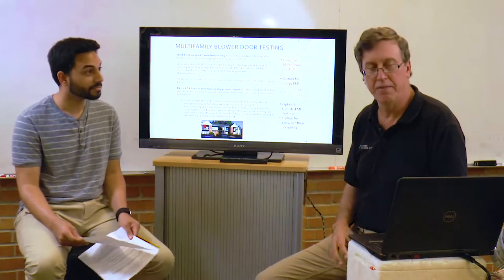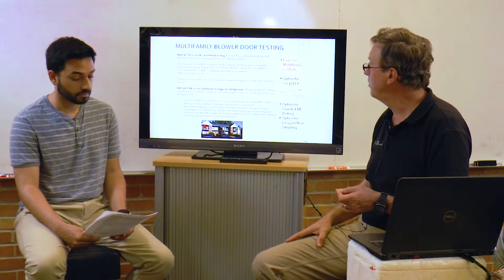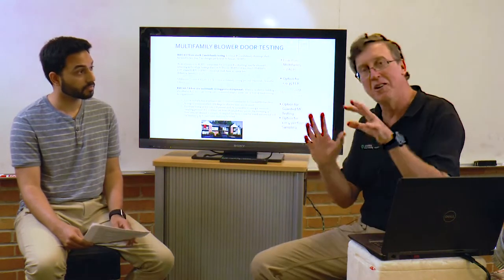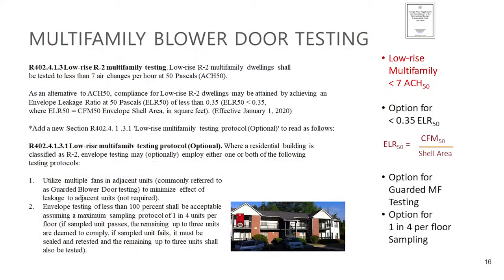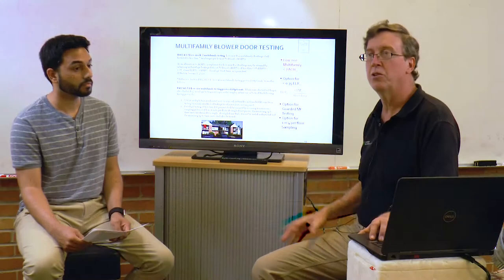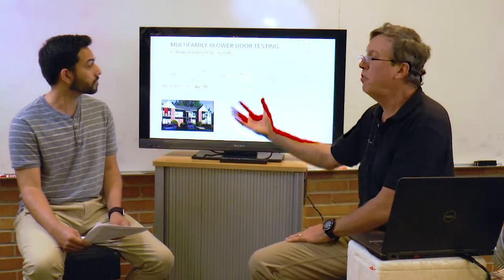And I think the other big thing is there's three important options that we have, and I think we should address each of these. So again, option, don't have to do it. You can test every single family unit to less than seven, you're good to go. But you do have this other option for a different metric. Instead of air changes per hour at 50 pascals, you can be less than the envelope leakage ratio at 50 pascals threshold of 0.35.